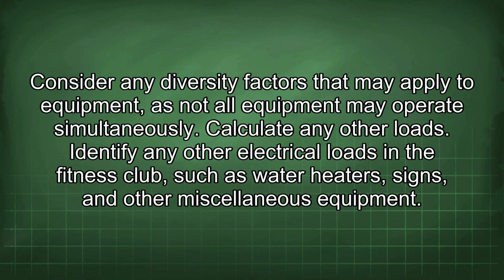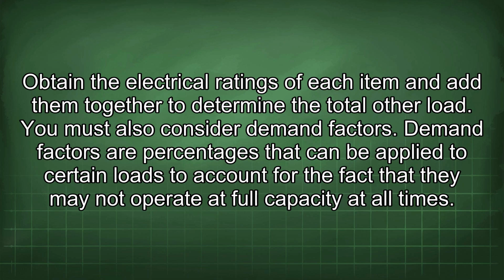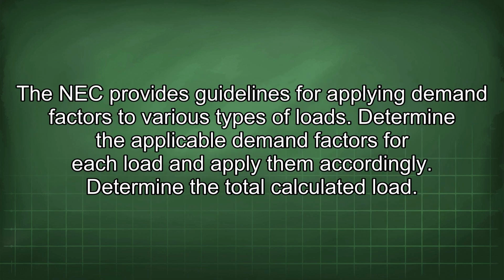Calculate any other loads. Identify any other electrical loads in the fitness club, such as water heaters, signs, and other miscellaneous equipment. Obtain the electrical ratings of each item and add them together to determine the total other load. You must also consider demand factors. Demand factors are percentages that can be applied to certain loads to account for the fact that they may not operate at full capacity at all times. The NEC provides guidelines for applying demand factors to various types of loads.